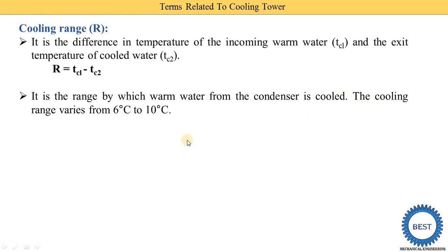The cooling range varies from 6 to 10 degrees centigrade. For example, suppose the inlet temperature of the warm water is 50 degrees centigrade. With R ranging from 6 to 10, the outlet temperature of the cold water we achieve is 40 to 44 degrees centigrade, depending upon the atmospheric conditions.